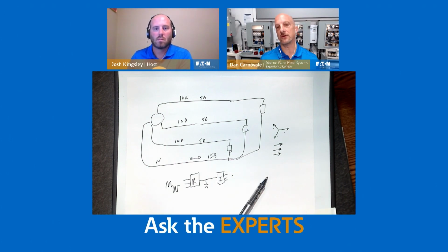So again, I'll get back to you on some of the details of that, but where I've seen this in larger industrials is the influence of those currents coming through, not the conductors themselves, because there are no conductors in your situation, but the capacitance to ground. They can follow that capacitive path, especially the higher frequencies. And that's why the EMI filter was likely recommended. And if it took care of the problem, that would make sense, because you're actually putting a conductor in parallel with that capacitance to ground. So, very complicated situation, but I'll definitely reach out to you and talk through the details of the answers to that.